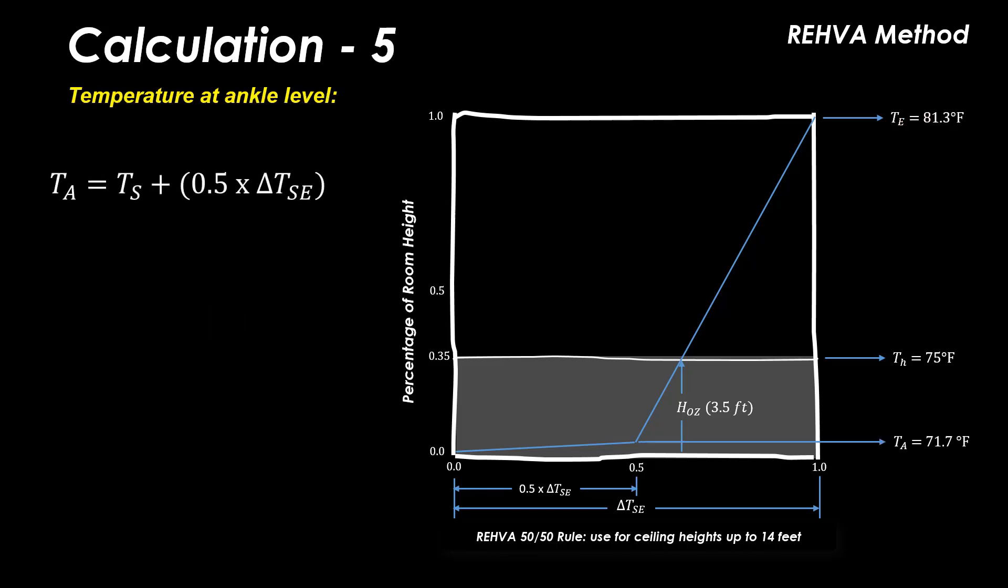Now the ankle level temperature can be calculated by adding half the overall supply exhaust delta T to the supply air temperature of 62°F, resulting in 71.7°F.